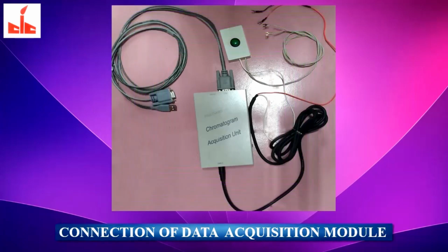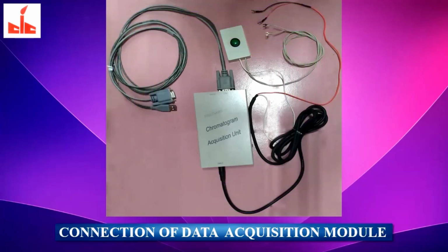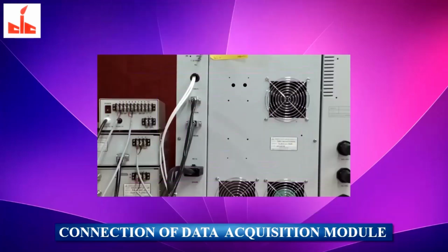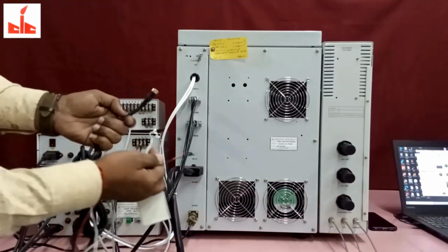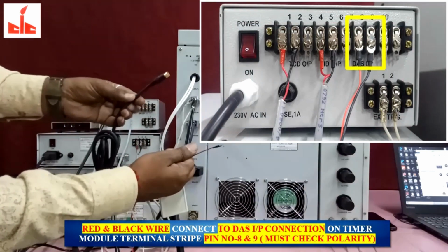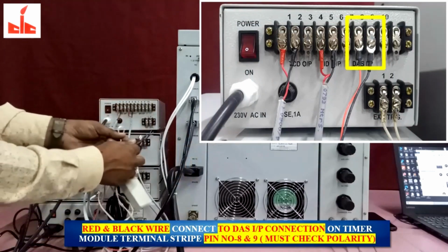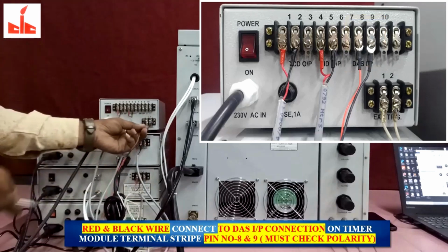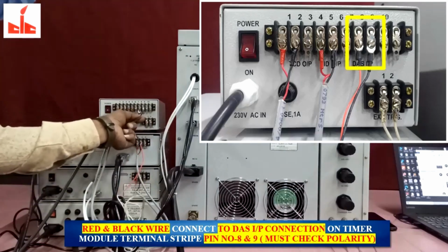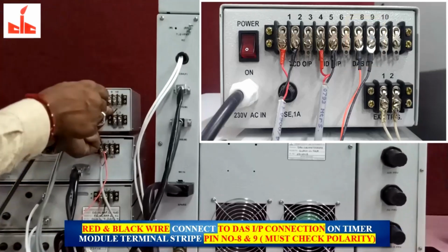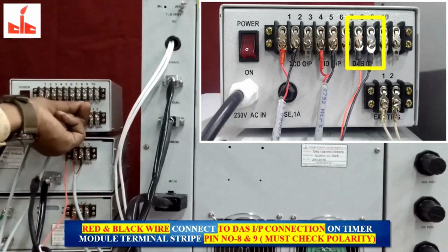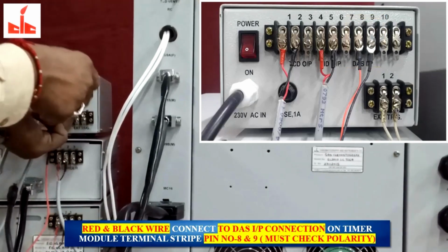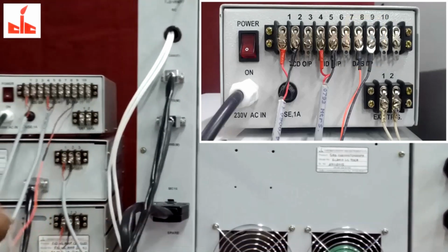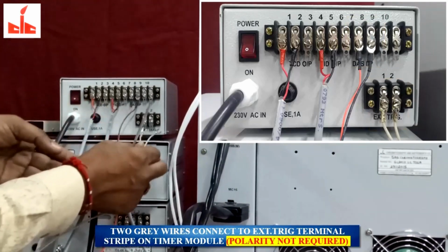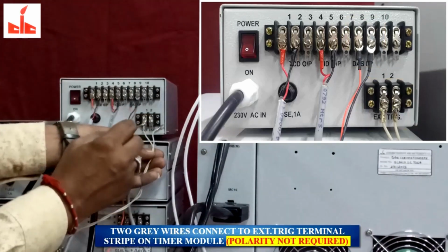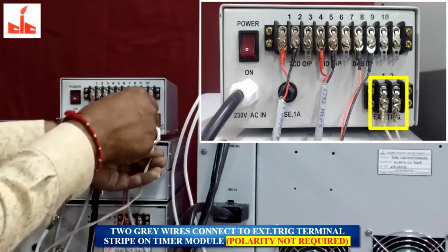Connection of data acquisition module. Red and black wire connect to DAS input connection on timer module terminal strip on pin number 8 and 9. Must connect as per polarity shown in the picture. Two gray wires connect to external trigger terminal strip on timer module, polarity not required.